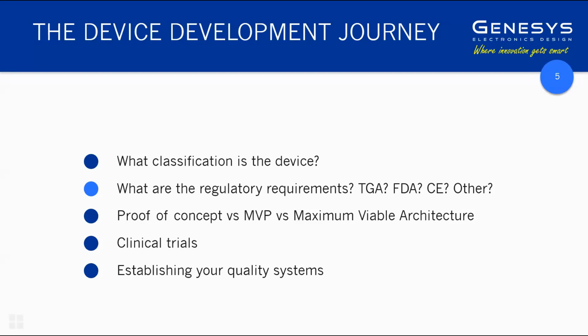And then I guess the large big bucket that a lot of people often don't think about is the whole quality systems aspect of it. It's considered, I guess, the biggest burden in developing active medtech products. If they weren't medical products, then almost half the work could be done away with. But because of the quality systems that are required and the proof required for getting regulatory compliance, there is a whole heap of work that has to be done.